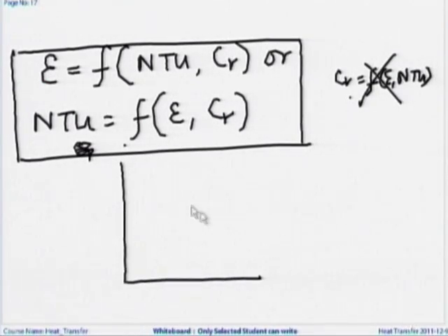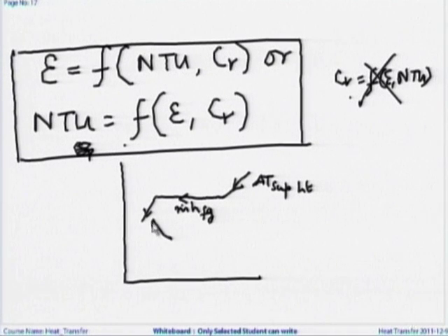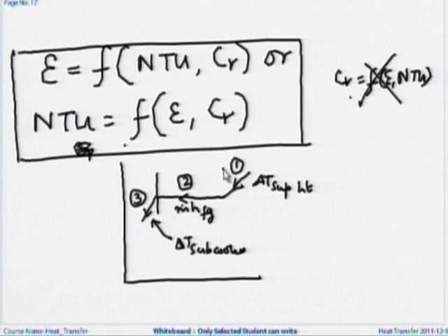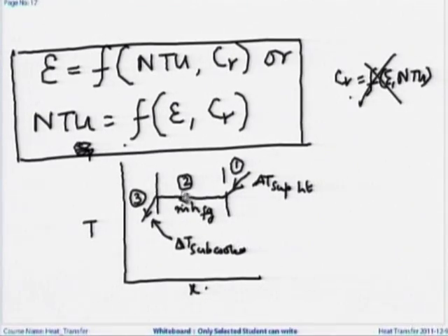Okay, professor. The question is, if I take a superheated vapor or subcooled liquid, then I will have some sensible portion and I will have a portion in which my temperature is constant. For the sensible portion, you design the heat exchanger as if you are designing for single phase flow, and then use the delta T LMTD approach for constant temperature. So, basically the heat exchanger design will be subdivided into three parts, subcooled, latent heat and the superheated portion. That is what essentially we do in design of condensers or evaporators. So, in this part the line is horizontal, that is all. We never said that the line is horizontal all through.